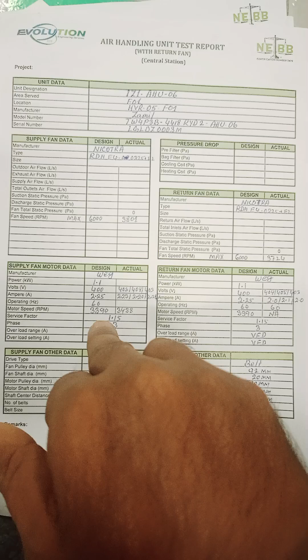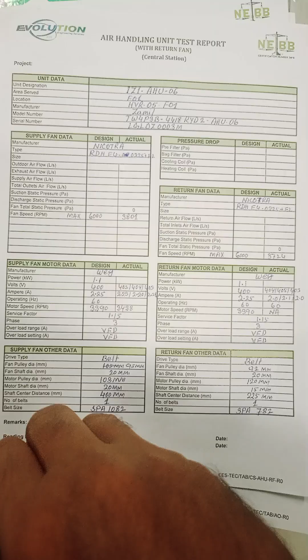Supply fan motor data. This one is supply fan only, return fan only. Now there is a motor which helps to rotate the supply fan. So we write it here for the supply fan motor. Actual will be here, design will be here, and we compare the difference. Return fan motor data, design will be here, actual will be here. Then supply fan other data, return fan other data. It means drive type, whether belt, fan pulley diameter, fan shaft diameter, motor pulley diameter, motor shaft diameter, shaft center distance. Shaft center distance means we measure the distance between the two shafts, the motor shaft and the blower shaft. After that, this is the basic data we collect from the AHU, from the nameplate of the supply fan motor, supply fan other data, and after that our work will be finished after balancing.